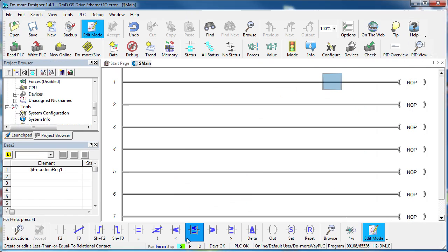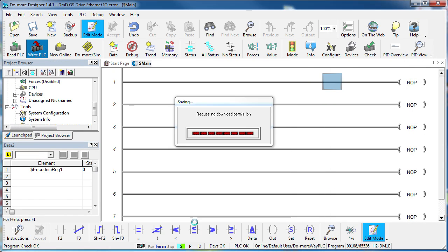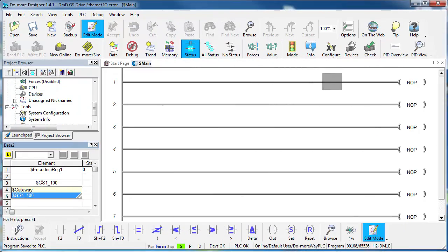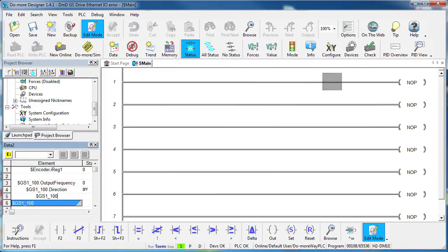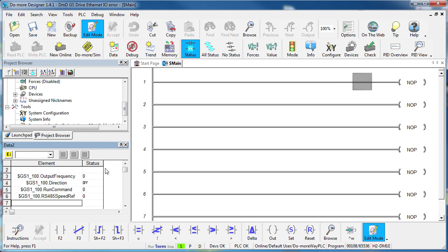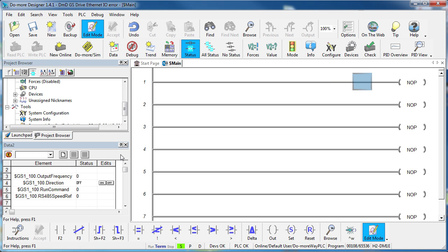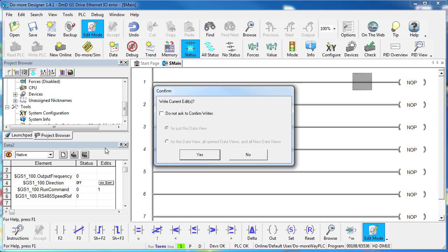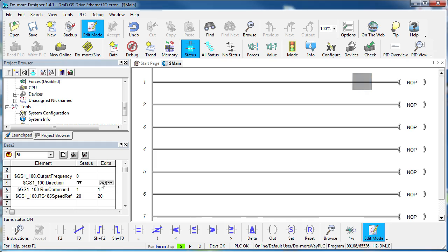Just for fun, let's download this configuration to the Do-more and test this device. In the data view, I'll add the GS1 drive's output frequency, direction and run command. Simply by setting these parameters in the data view, I can control the motor in the drive. And remember, the Do-more set all of this up for me. All we did was enable the Ethernet IO and scan for the drive.